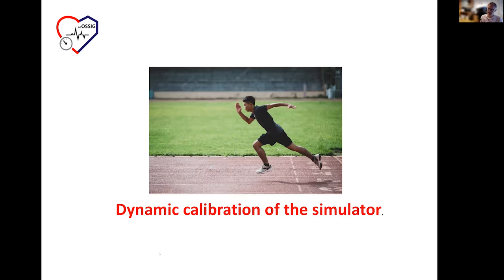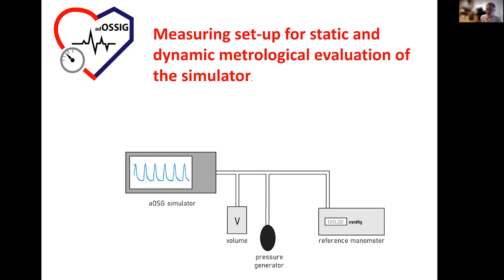Dynamic calibration means that now we are testing the outputs, so these waveforms of the simulator. Or to put it even more simply, the simulator is a generator which generates pressure pulses. And now we would like to evaluate and somehow calibrate these pressure pulses. Dynamic calibrations are, in the world of national metrology institutes, quite seldom because they are quite complex.